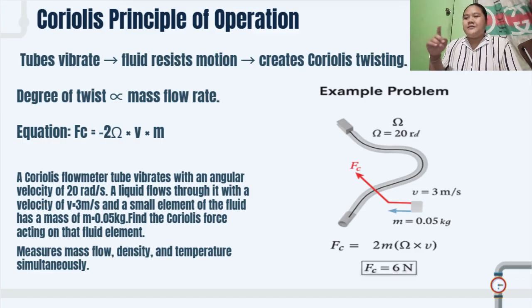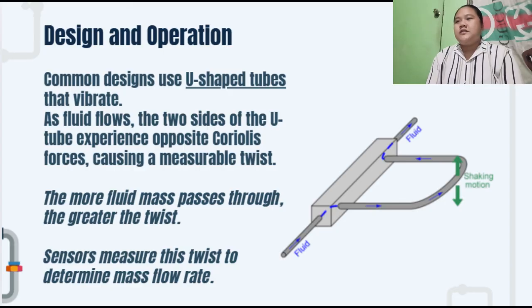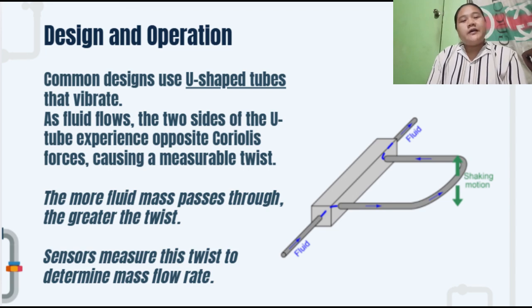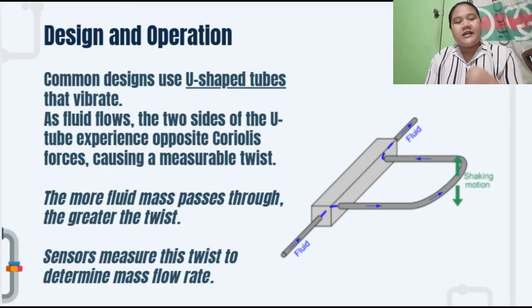So, may example problem na da guys, kung paano nyo na sa i-apply nga formula. So, design and operation. Common designs use U-shaped tubes that vibrate. So, nga U-tube gid ang ginagamit. So, kaya ang U-tube mo sa pinaka-effective nga form sang pipe para ma-detect ya ang vibration kay twisting nga ginadala ni Coriolis effect. So, the more fluid mass passes through, the greater the twist, and sensor measure this twist to determine mass flow rate.